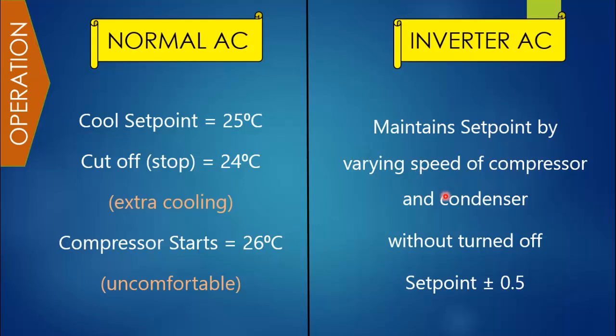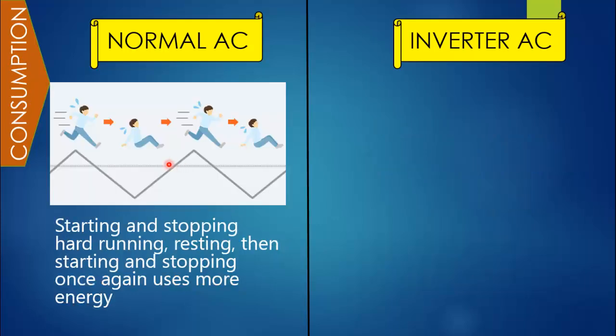Whereas the inverter AC maintains the setpoint by varying the speed of the compressor and condenser without turning off. It will change its speed around the setpoint plus or minus 0.5°C, so it will maintain the room temperature around 24.5 to 25.5°C without ever turning off.